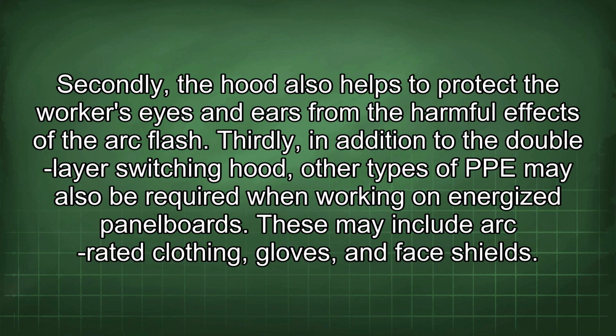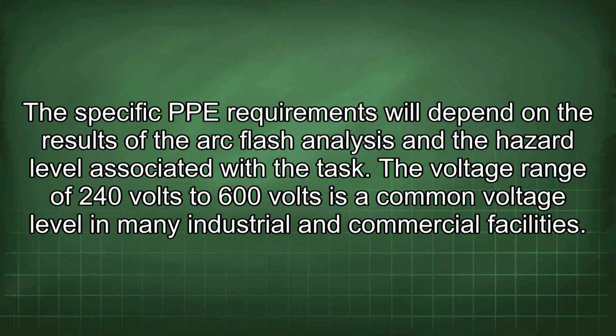Thirdly, in addition to the double-layer switching hood, other types of PPE may also be required when working on energized panel boards. These may include arc-rated clothing, gloves, and face shields. The specific PPE requirements will depend on the results of the arc flash analysis and the hazard level associated with the task.